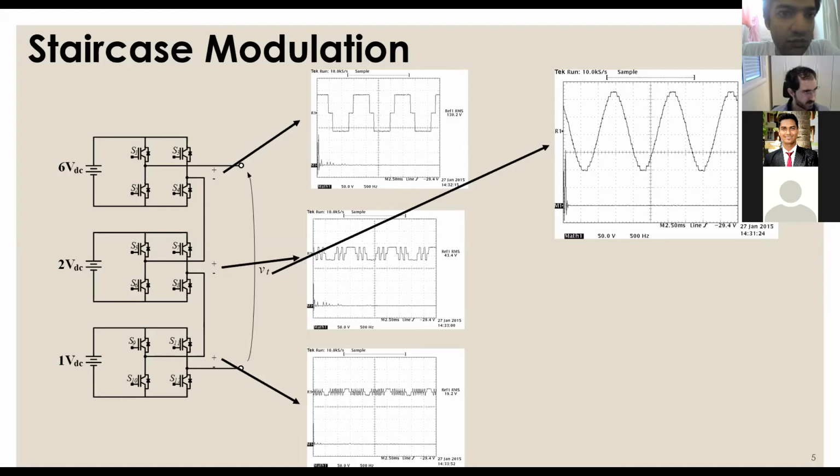One module has to transfer large portions of power to the grid, then it means you need high rating devices at that module, then I think it should not be used for bulk power because it looks like a disadvantage. No, of course, it's the contrary. If you are processing this amount of power, bulk power, with low switching frequencies, if you have a great amount of power, you can use other kinds of technologies here, like thyristors.